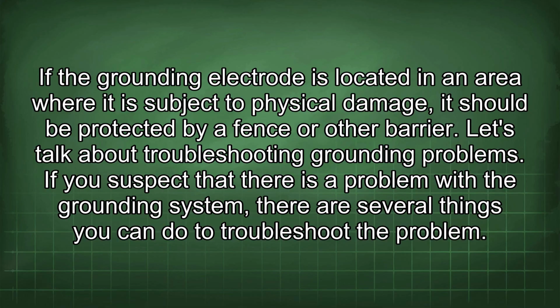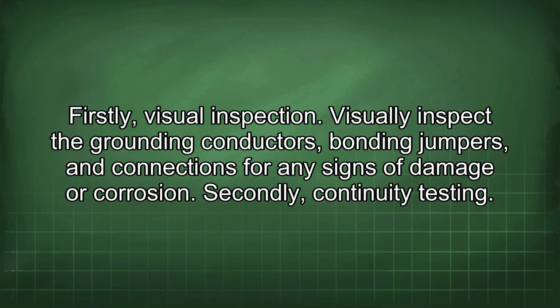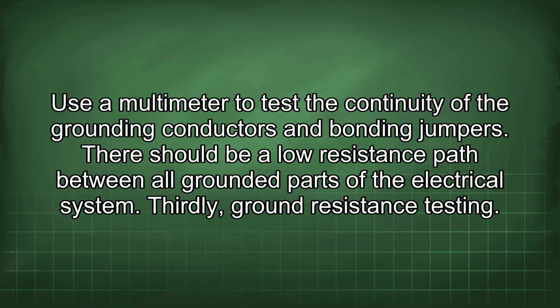Let's talk about troubleshooting grounding problems. If you suspect that there is a problem with the grounding system, there are several things you can do to troubleshoot the problem. Firstly, visual inspection. Visually inspect the grounding conductors, bonding jumpers, and connections for any signs of damage or corrosion. Secondly, continuity testing. Use a multimeter to test the continuity of the grounding conductors and bonding jumpers. There should be a low resistance path between all grounded parts of the electrical system.